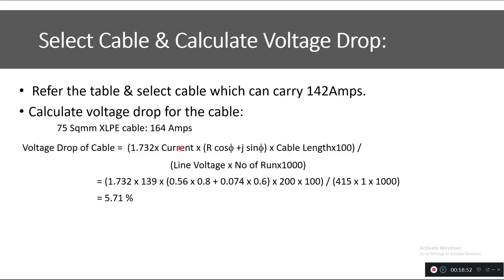The voltage drop formula requires resistance, reactance, line voltage, current, number of runs, and cable length of 200 m. Substituting the resistance and reactance values from the datasheet, with cosφ = 0.8 (and sinφ derived from it), the voltage drop for the 70 mm² cable calculates to 5.71%. Since this exceeds our 5% limit, we will not use the 70 mm² cable.